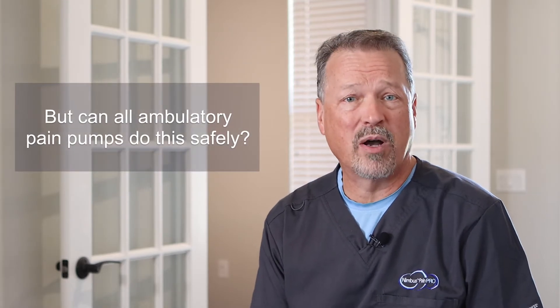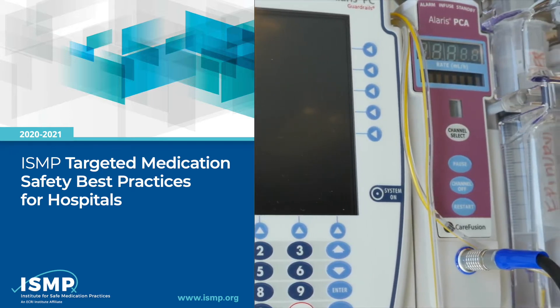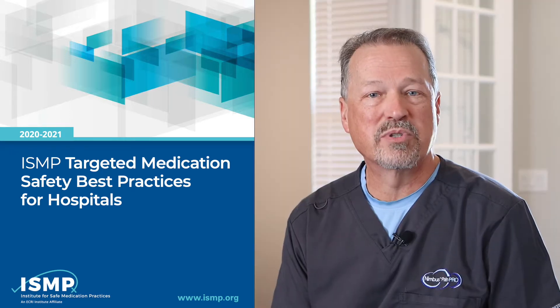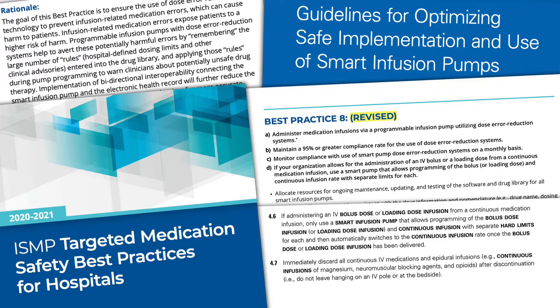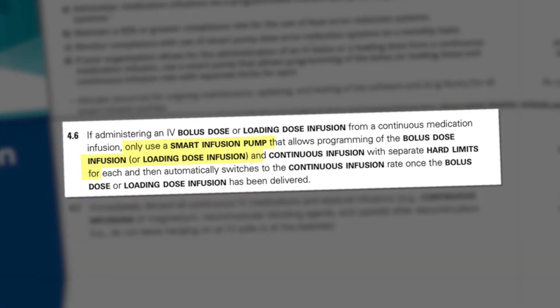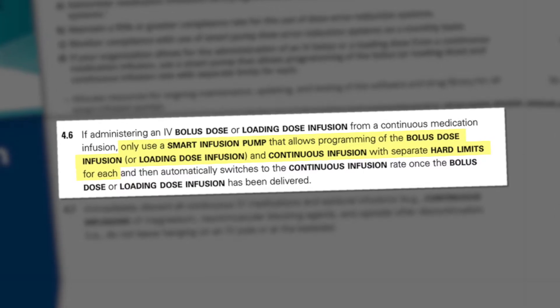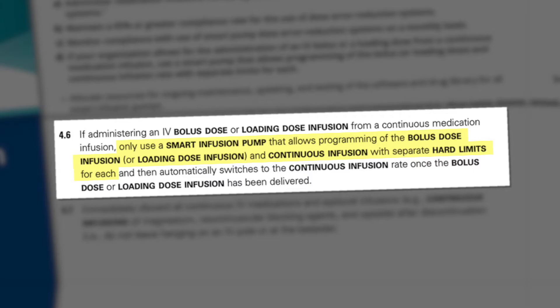But can all ambulatory pain pumps do this safely? In 2021, the Institute for Safe Medication Practices published best practices for smart infusion pumps and infusion pumps that can deliver PCA boluses and intermittent boluses. ISMP's best practice 8D recommends that your facility use a smart pump that allows programming of the bolus or loading dose and continuous infusion rate with separate limits for each.